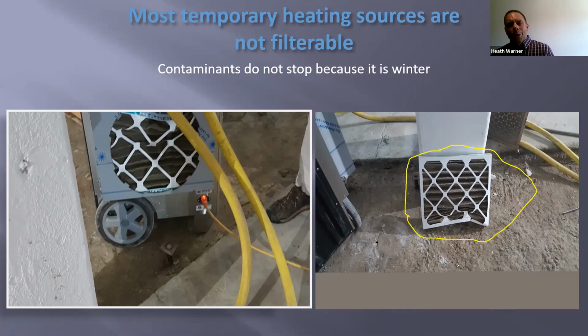So what I tell everybody, when we start talking about using permanent HVAC systems, remember the picture we had a little while ago about all those rooftop units and how simple it was to just crawl up on the roof, take your little nut driver with you, zip, zip, zip, and change your filter. If these filters are on temporary equipment at ground level, and literally all you have to do is slide them in and out, how often do you think permanent HVAC system filters are actually being changed on job sites?